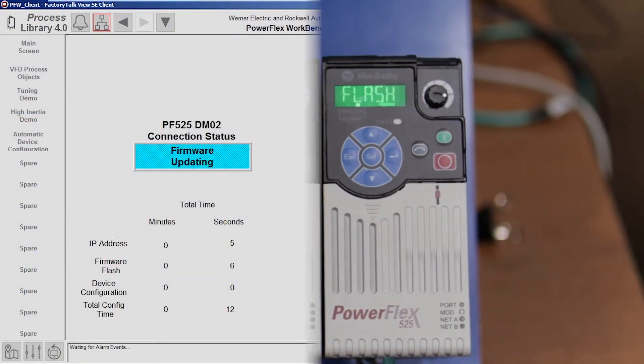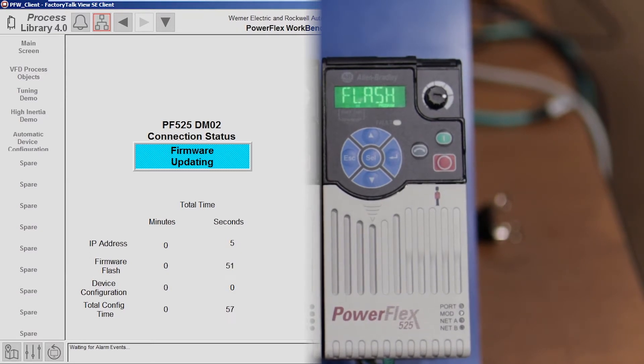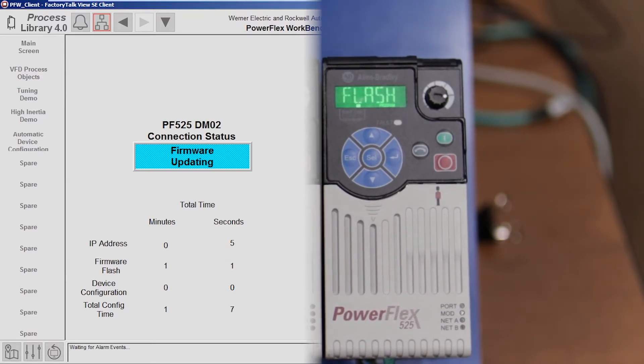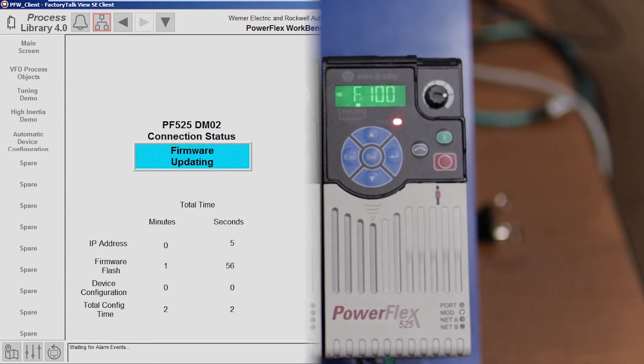Once the cable is connected into the Stratix switch, the IP address is downloaded automatically from the Logix controller. Once that's done, then ControlFLASH in the controller will flash the firmware on the new drive to match the firmware of the existing drive. And finally, once the flash is done, the program will be downloaded directly from the controller to the new drive.